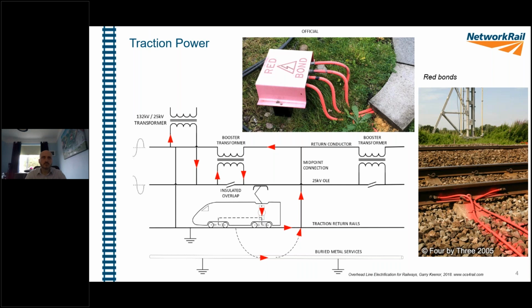Other things that we may have around here is something known as a return screen conductor. This is ultimately there to reduce any EMC, electromagnetic compatibility, issues, which predominantly will cause issues on the signaling and telecoms cables, and may cause wrong side failures of that equipment.